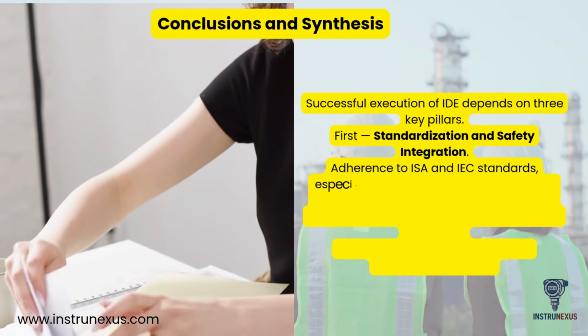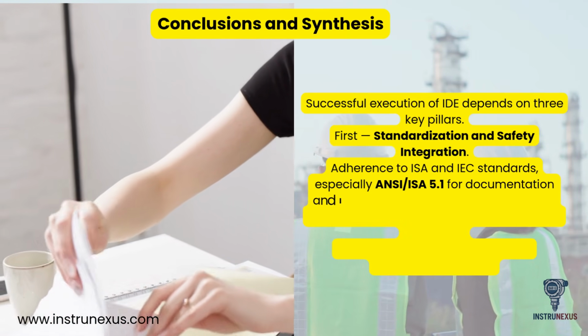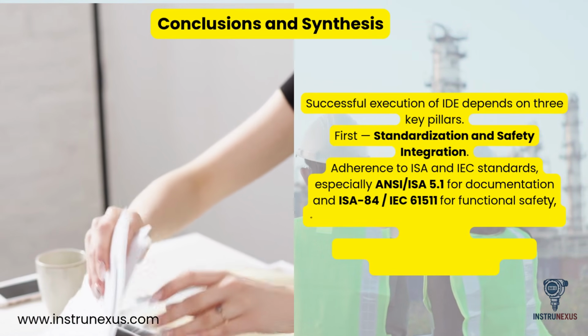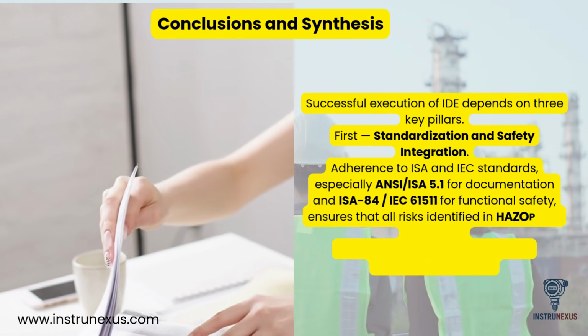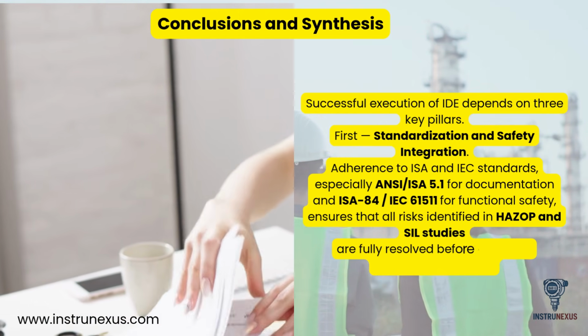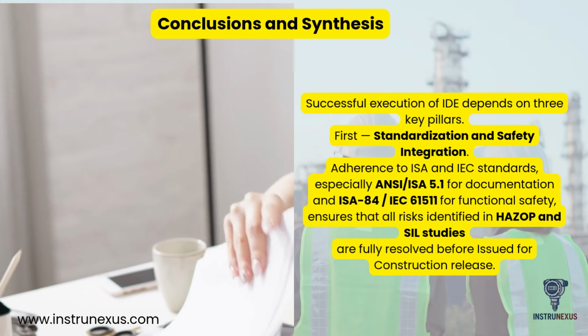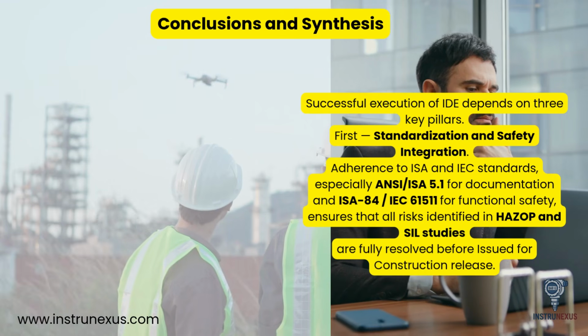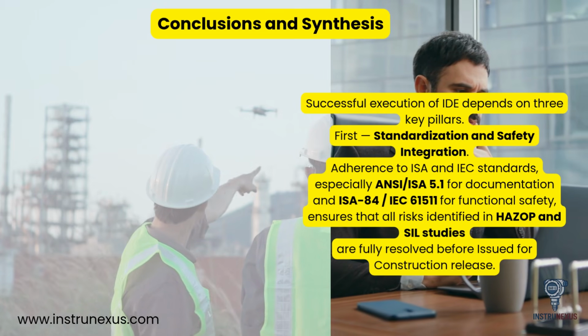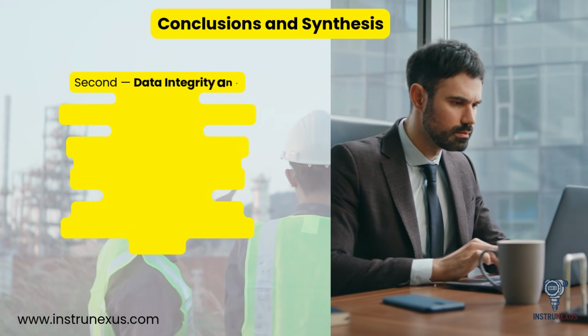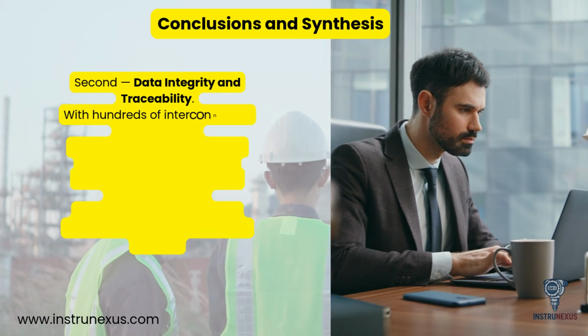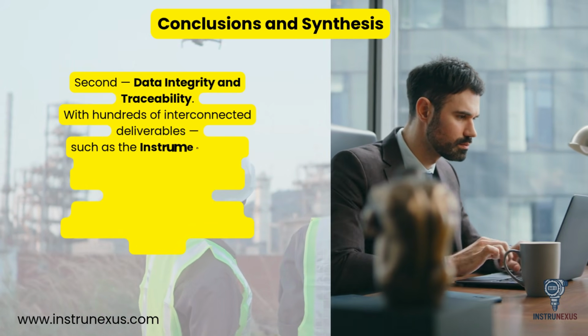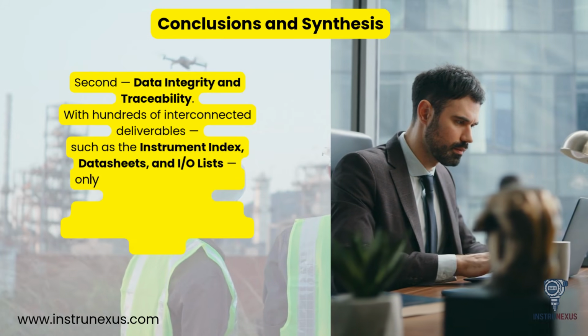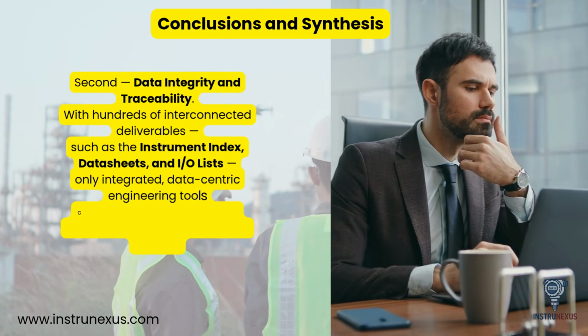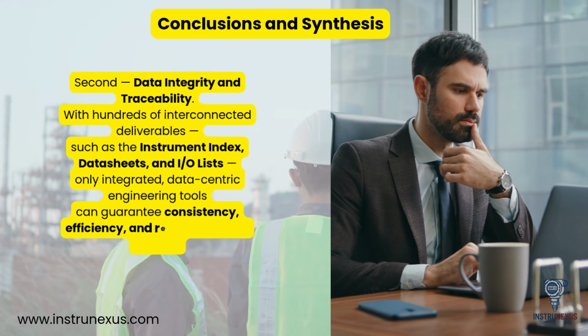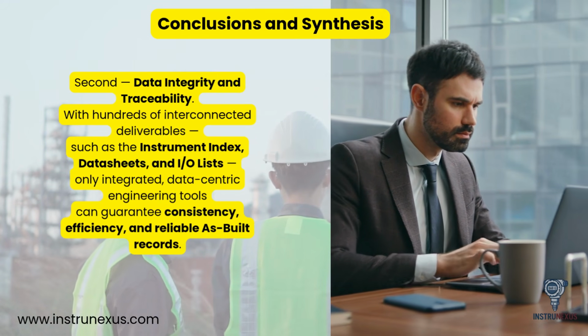First, standardization and safety integration. Adherence to ISA and IEC standards, especially ANSI ISA 5.1 for documentation and ISA 84 IEC 61511 for functional safety, ensures that all risks identified in HAZOP and SIL studies are fully resolved before issued for construction release. Second, data integrity and traceability. With hundreds of interconnected deliverables, such as the instrument index, datasheets, and I/O lists, only integrated, data-centric engineering tools can guarantee consistency, efficiency, and reliable as-built records.